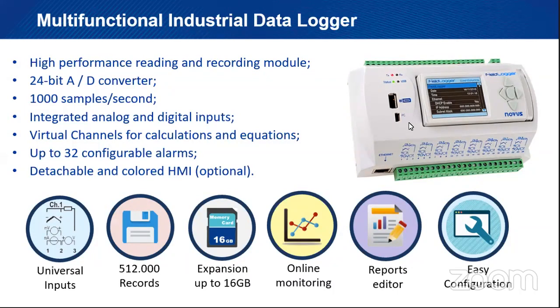Then we have the milliamps input for linear inputs, so pressure transmitters, differential pressure transmitters, level transmitters. These are the ones you get most on milliamps, flow transmitters as well, so millivolts, volts, and that in lots of different ranges. This is a very important point on the field logger, okay? It has 8 of those analog universal inputs plus 8 digital IOs and 2 relay outputs, okay?